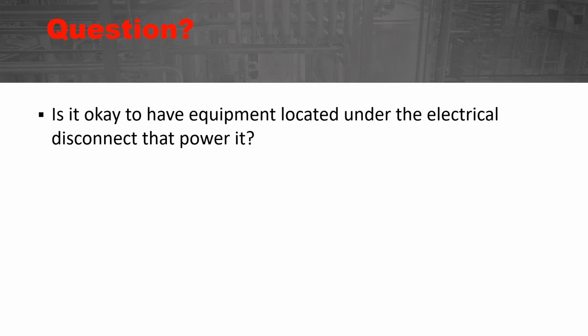National Electrical Code, putting electrical disconnect or electrical equipment under a disconnect. We have to be careful of Article 404, 404.8, which covers accessibility and grouping. And it says all switches and circuit breakers. Basically what this is saying is the center point of the handle of the disconnect can be no more than 6 foot 7 inches above the floor or working platform. And so we've got to be careful as long as the disconnect is up and no more than 6 foot 7 inches to the handle, the midway of the handle, then it's fine.